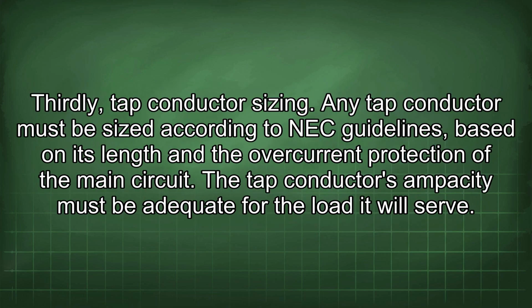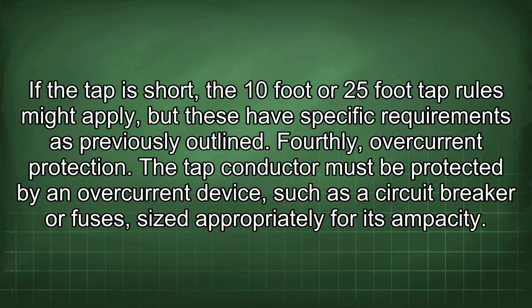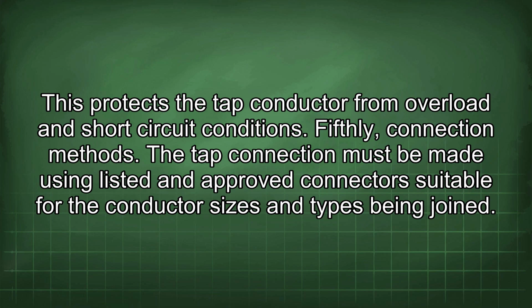Thirdly, tap conductor sizing. Any tap conductor must be sized according to NEC guidelines based on its length and the overcurrent protection of the main circuit. The tap conductor's ampacity must be adequate for the load it will serve. If the tap is short, the 10-foot or 25-foot tap rules might apply, but these have specific requirements as previously outlined. Fourthly, overcurrent protection. The tap conductor must be protected by an overcurrent device, such as a circuit breaker or fuses, sized appropriately for its ampacity. This protects the tap conductor from overload and short-circuit conditions.